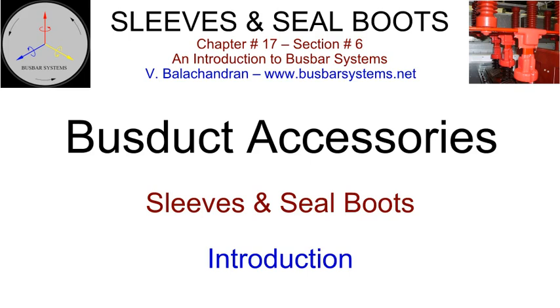Introduction. Many specifications call for conductors to be sleeved or coated with an insulating compound. Seal boots are installed in the run of the conductor wherever they stand exposed, such as at bolted joints, expansion joints, and terminations. In many designs, where the conductor insulation is an integral part of the overall basic insulation level of the enclosed bus, the design of the seal boot assumes more importance.